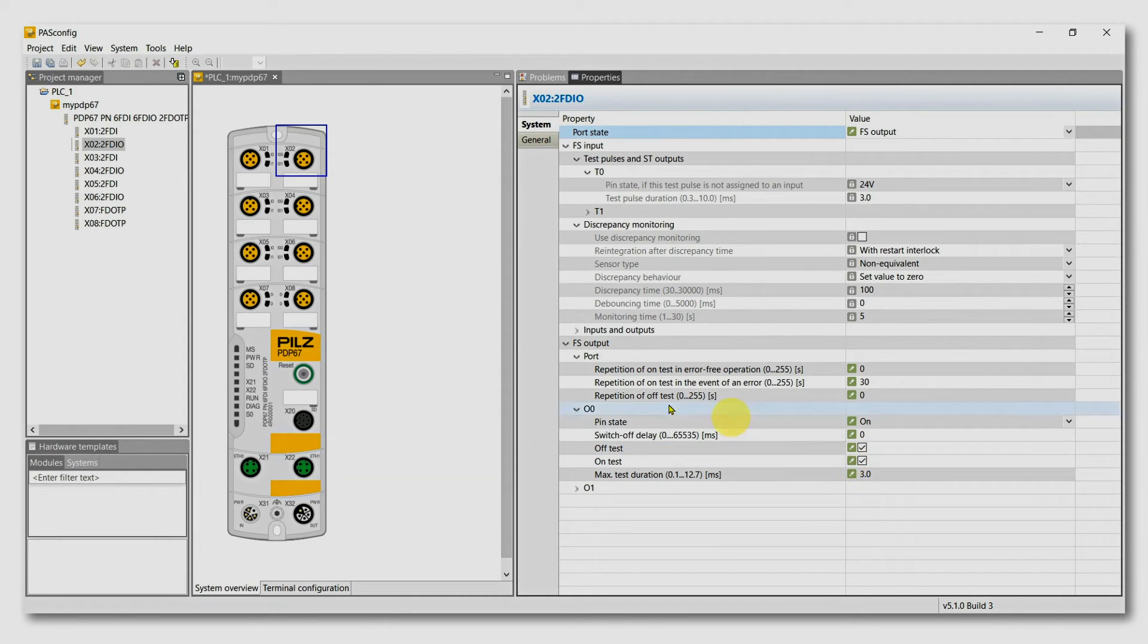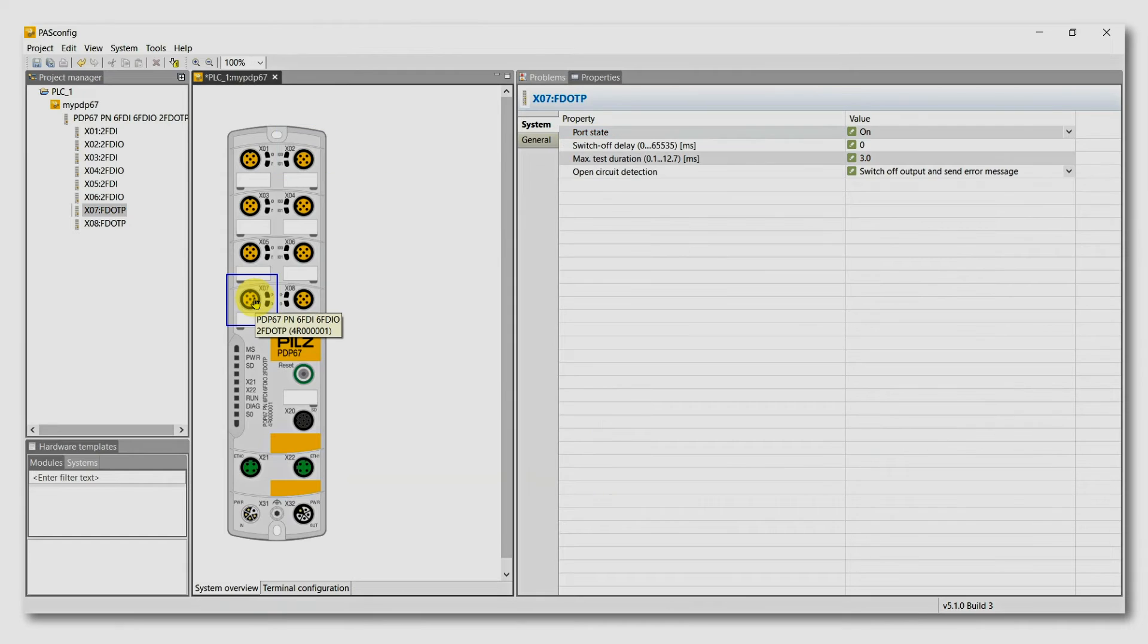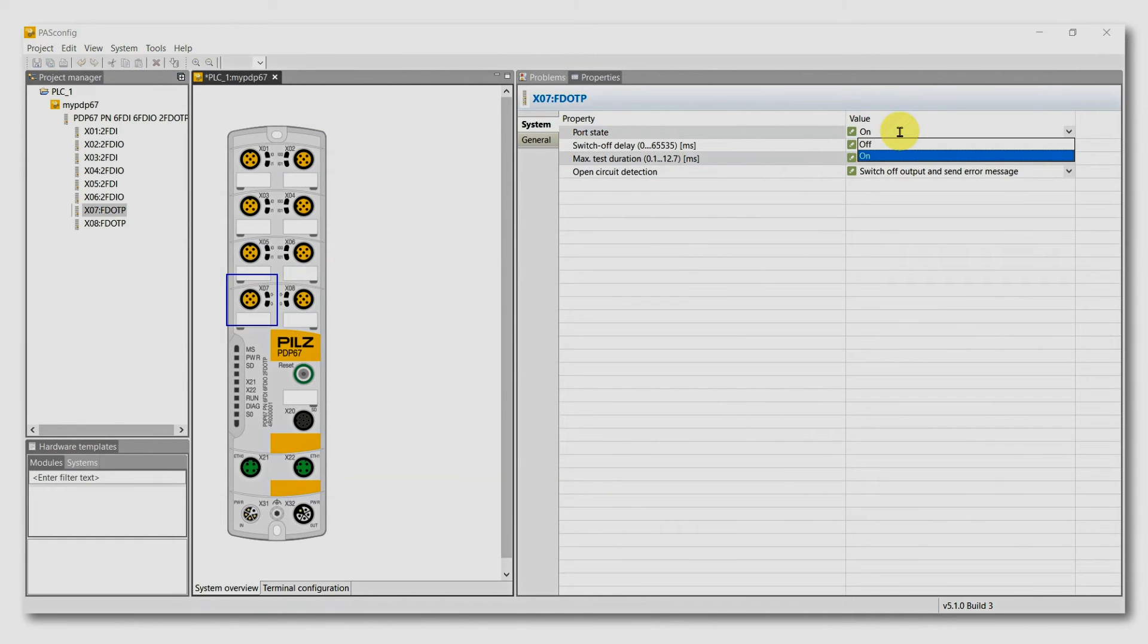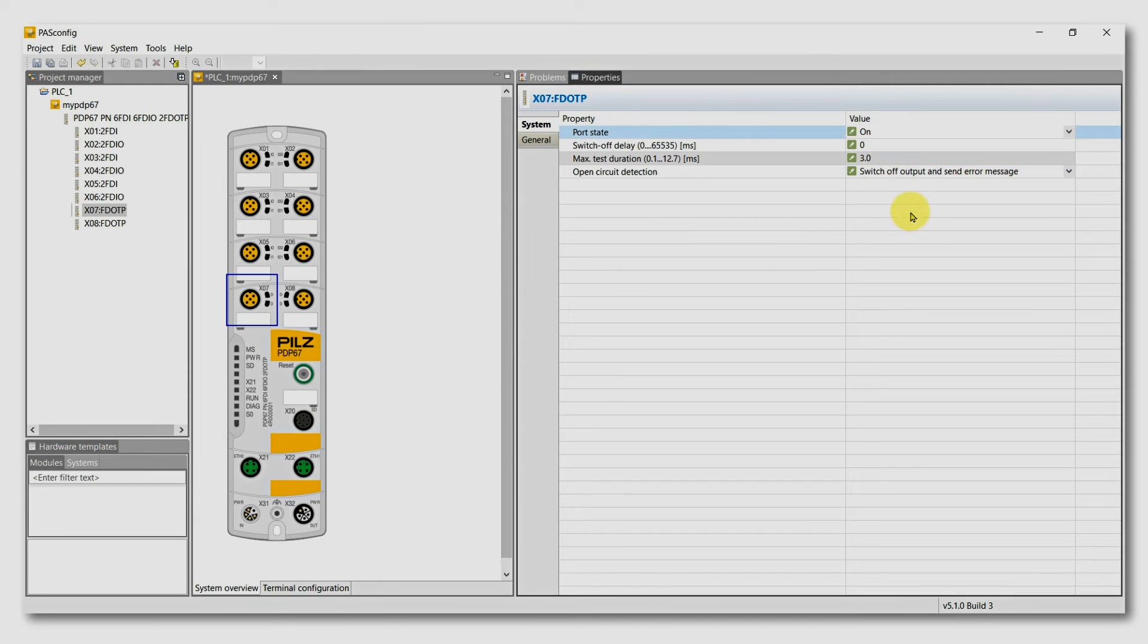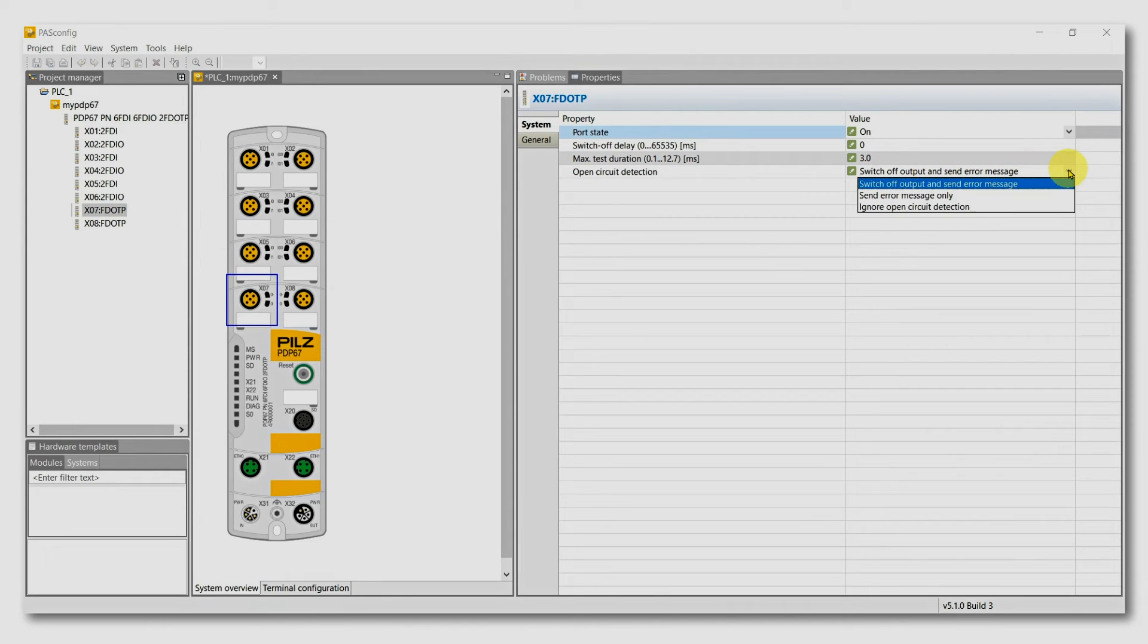Looking at the two pole output ports, X7 and X8, you can activate or deactivate them. But what is more important, you can choose if broken wire should cause an error or a warning or should be ignored.